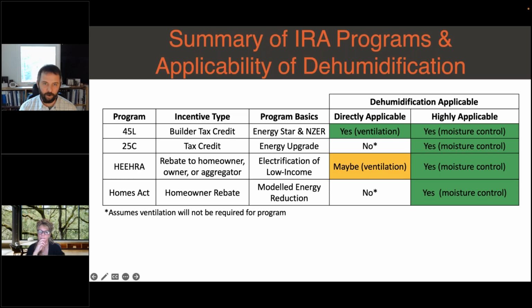Some of the standards, the way they're written, show that they can go higher, but if you measure them in the field, they transfer about 50% of the moisture from the outgoing to the incoming air. And in research that I've done in the past, if you do not have a good AC system or a good way to control the interior RH, ERVs do not maintain that delta enthalpy or energy they need in order to get good transfer amounts in the humid months. And so you see inside and outside approaching each other because we don't have that delta that we need for ERVs to work well. And so typically in the projects I work on, if I put an ERV in the south, I also put a dehumidifier because we need to maintain that delta enthalpy for it to work well.